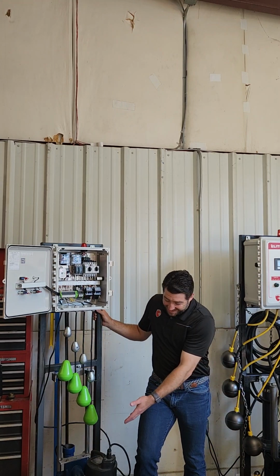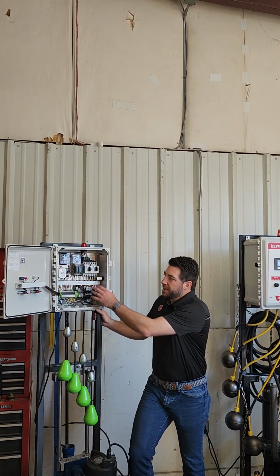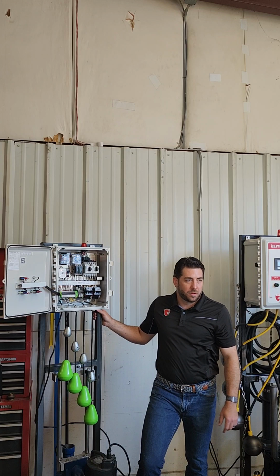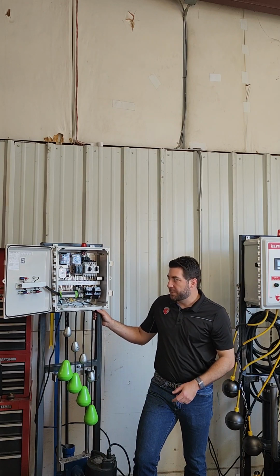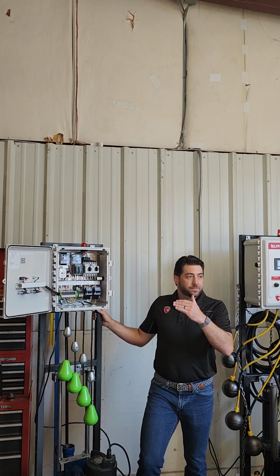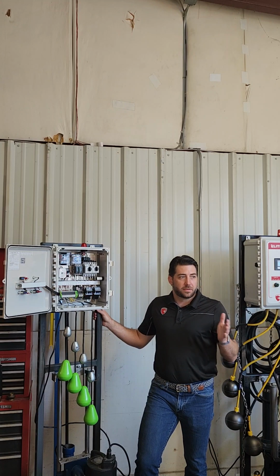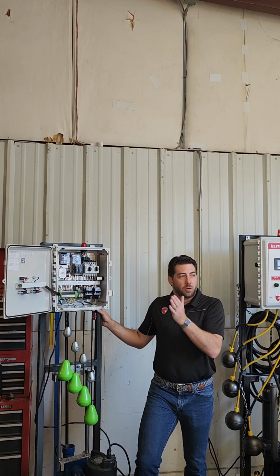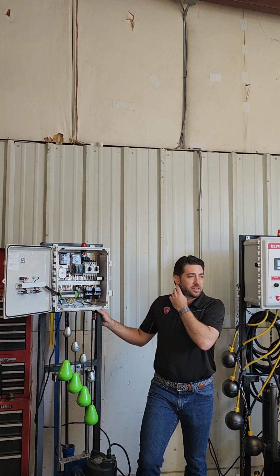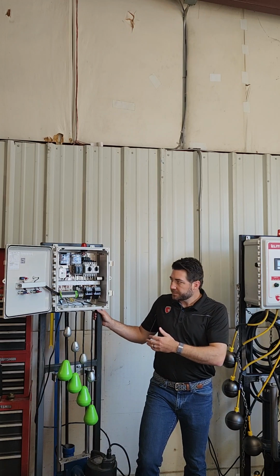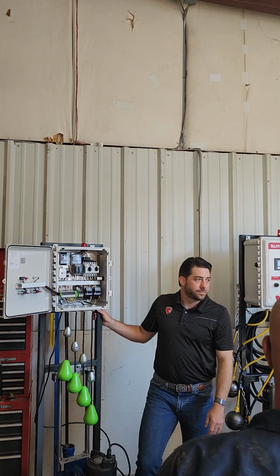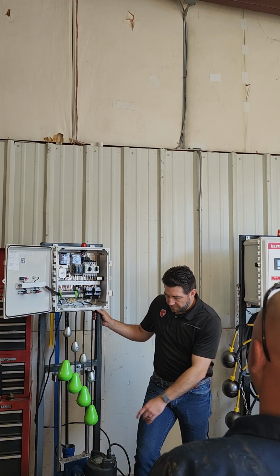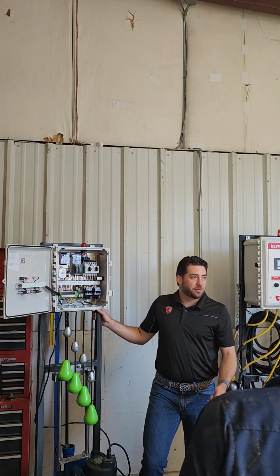Otherwise, you pull it and look at it. But if you don't have the overload set to the full load amps of the pump, if it's above it, then you're going to be running the pump overloaded without it tripping, right? So you're not getting that same burn. So it could potentially damage the pump if you set that too high. If it's too low, it's going to trip out early.